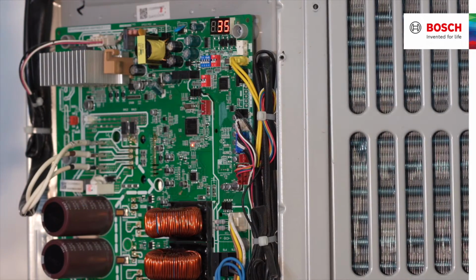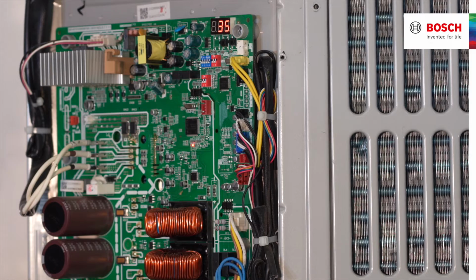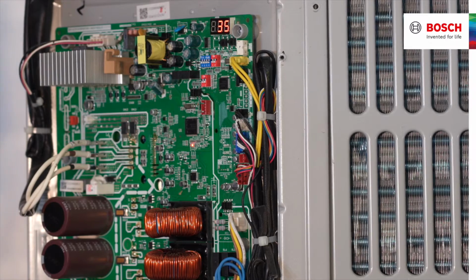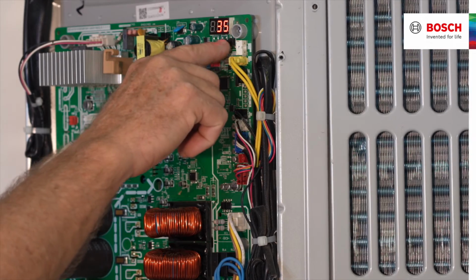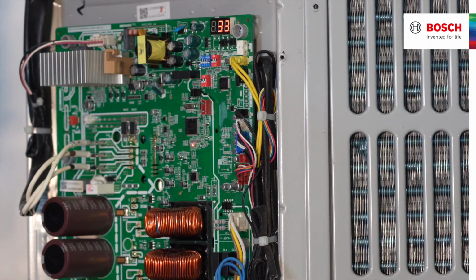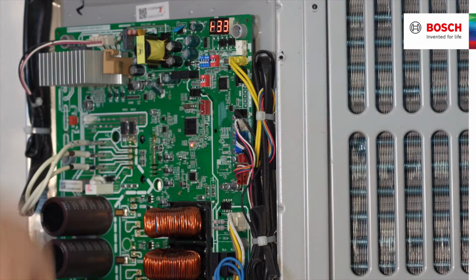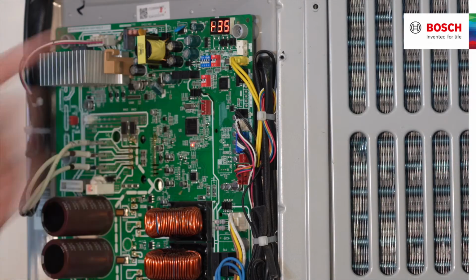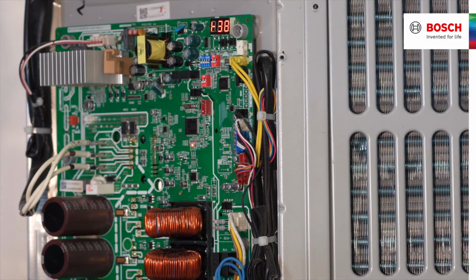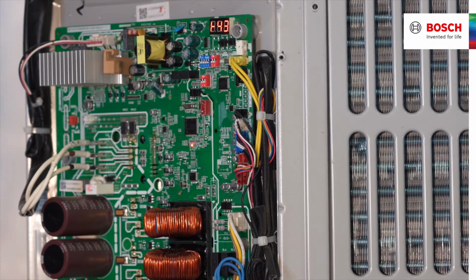Ken, we've got this unit running. We're now going to go through the system parameter check, just like we would in a commissioning, a maintenance, or even a service call situation. Right now the machine is running at 35 Hertz. I could push the force button and do the numbers. So let's do that. I'm going to go up here to SW on this particular unit, it's SW1. Now this is a 15 SEER. I'm going to give it a short push. You see the sideways T, and then it is going to ramp up toward the 100% mark of this particular unit.